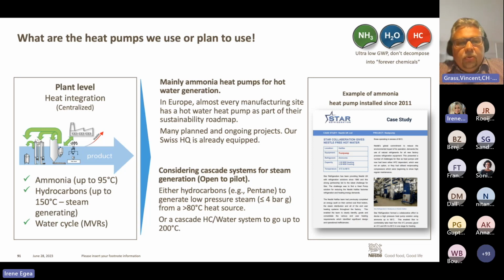So we do deploy these solutions, like I mentioned, as part of our sustainability journey. Now they are identified in almost each and every factory. And then for factories that have a steam demand, say for sterilization or even higher temperature, here we see basically two options. One is to work with a steam generating heat pump using hydrocarbon as a refrigerant, so pentane if it's to go up to 145, 150 degrees, or a cascade system, as was also mentioned earlier, between a hydrocarbon cycle and then a water cycle, so a steam compressor: make the water boil and then compress it to reach the temperature you need. So that's the direction we are currently taking with regard to heat pumps.